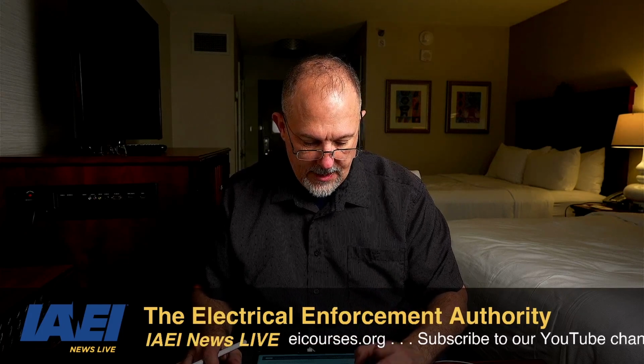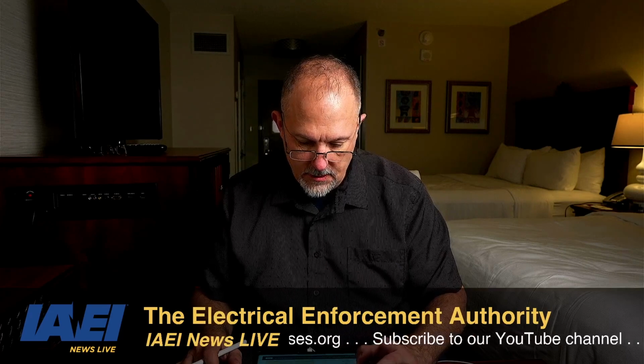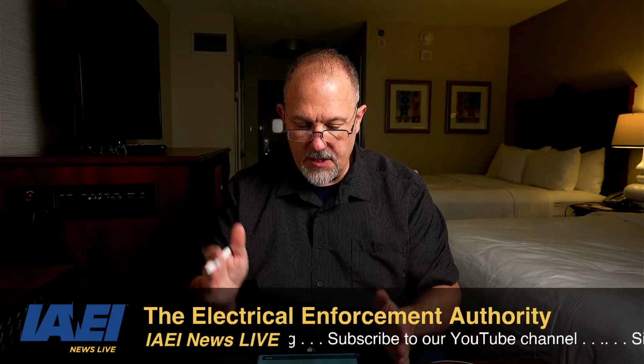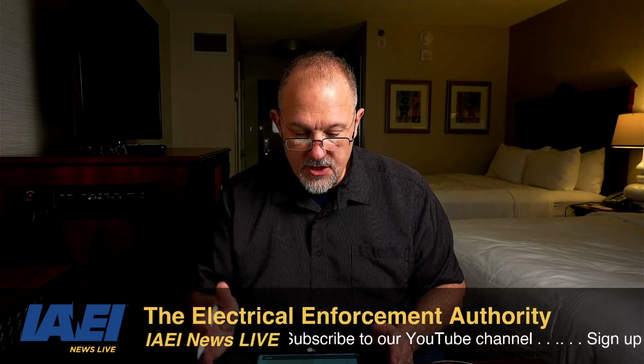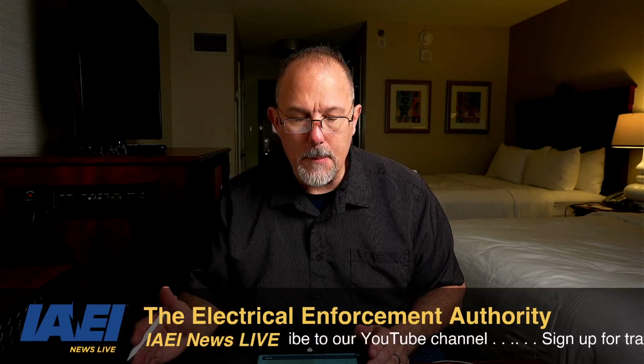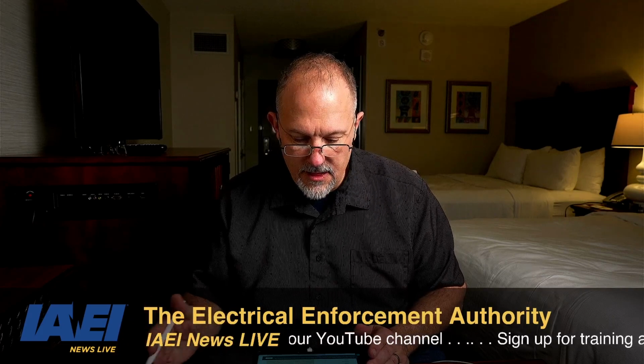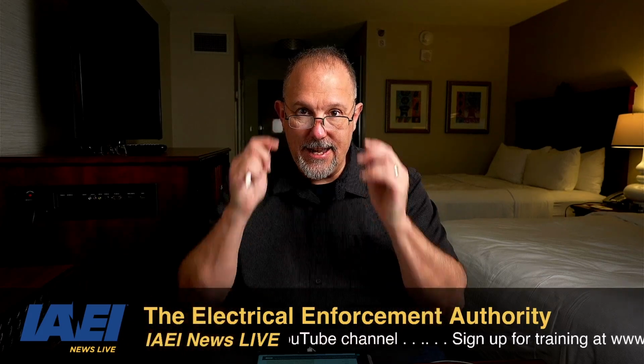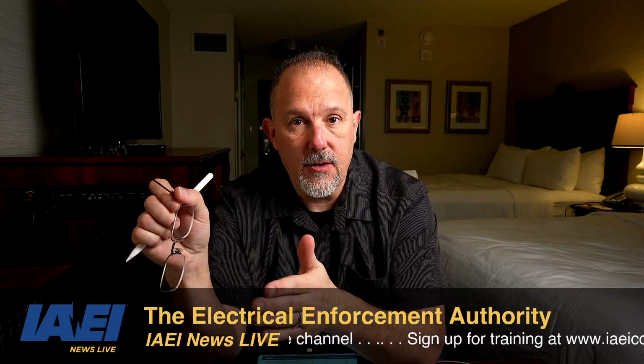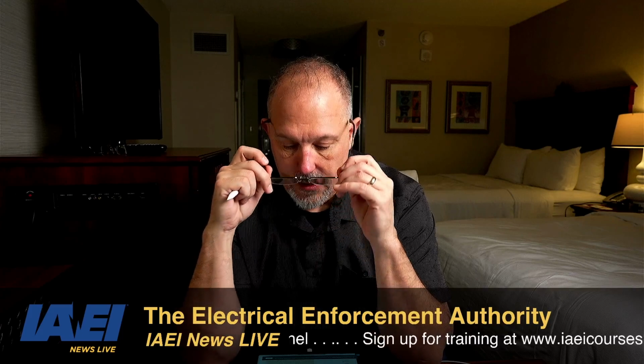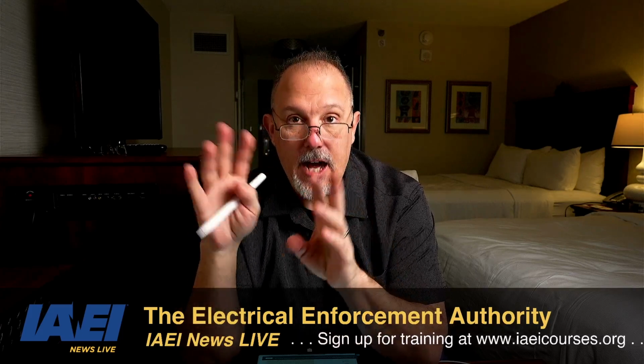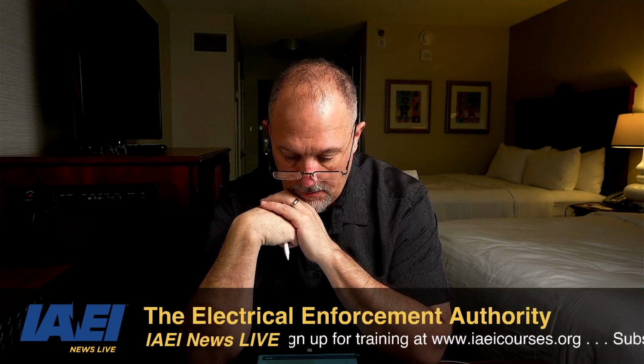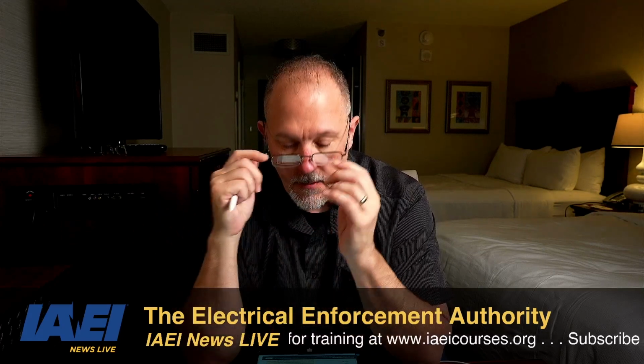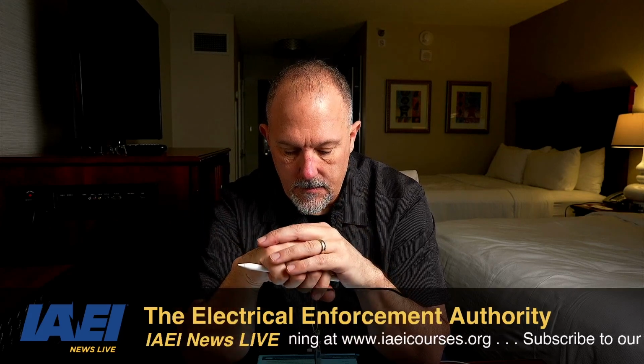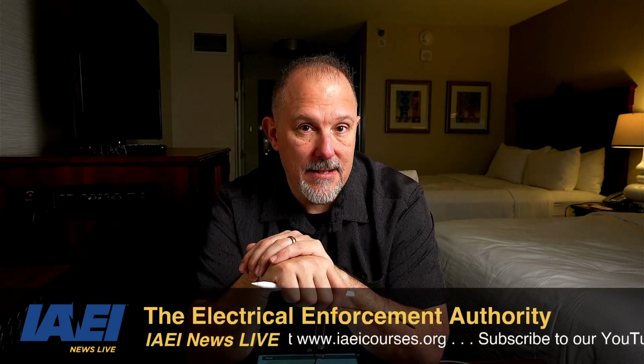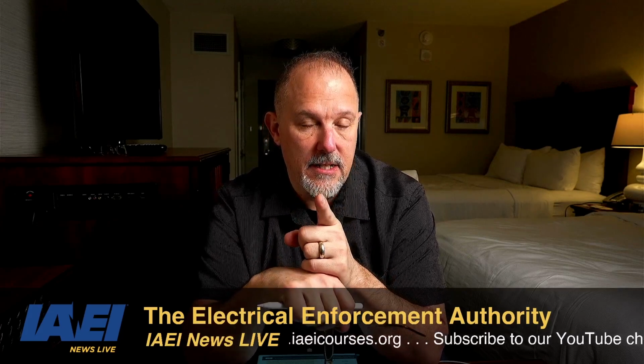So a feeder, look at feeder: all circuit conductors between the service equipment, the source of a separately derived system or other power supply source, and the final branch circuit overcurrent device. Now, we know that the generator is at least an other power supply source. So we know that much to be true. So now the question is, is it a separately derived system or not? We're going to get into that discussion as well.